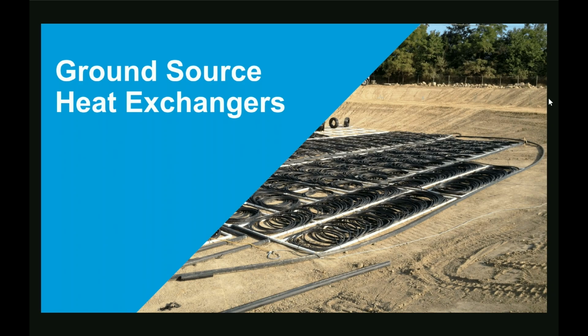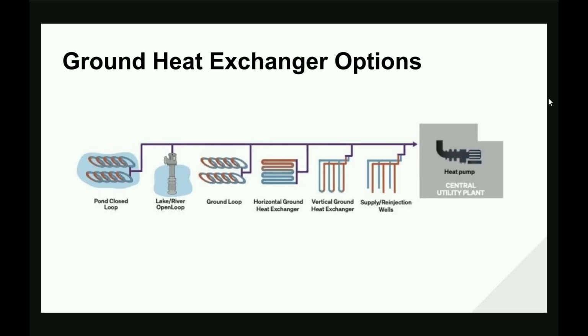Ground source heat exchangers, every site's different, you really have to understand your formations. I've done every type of these heat exchangers on many projects: open loop, closed loop, slinkies, directional bore. When you start looking at the cost, your open loops are the most inexpensive. Lakes, rivers, we drop a turbine pump into a wet well, pump the water out, and then discharge it back in. It's a very low cost option.